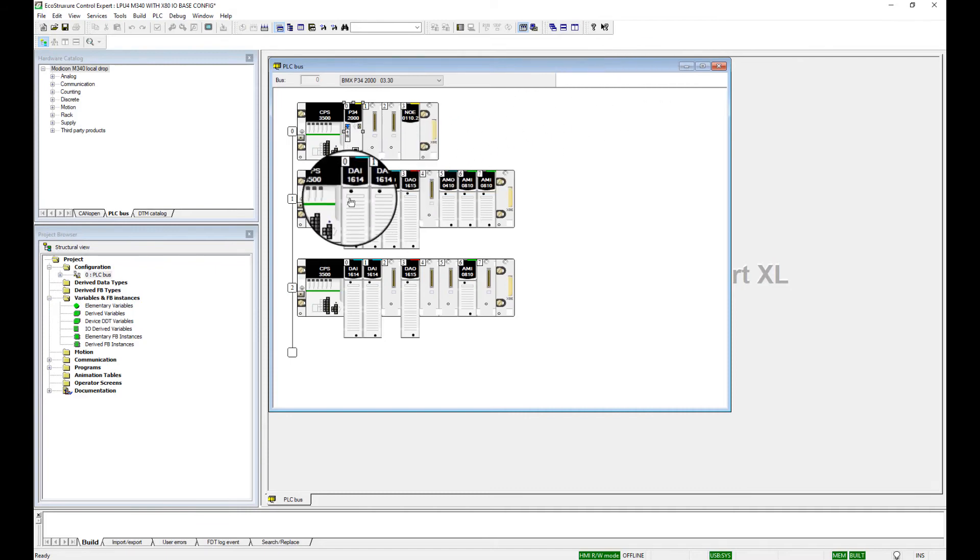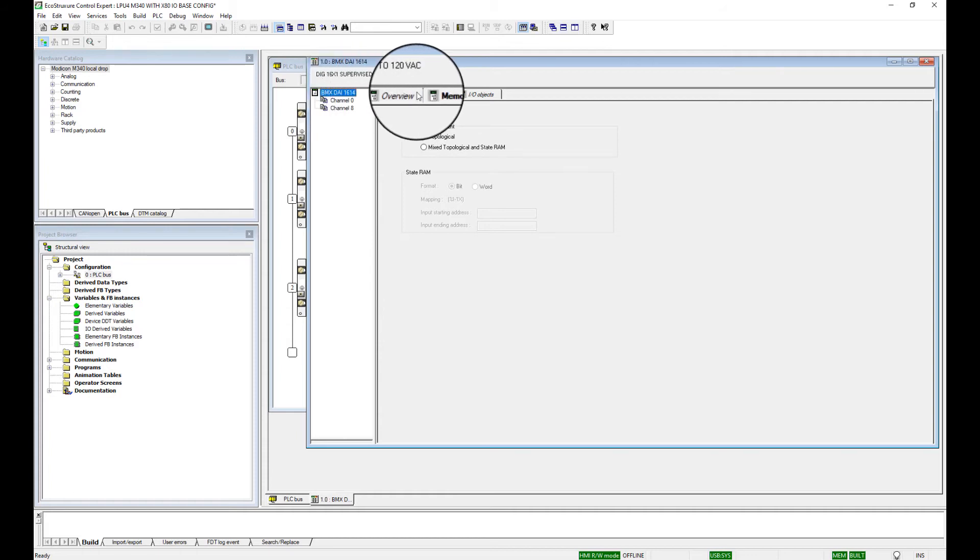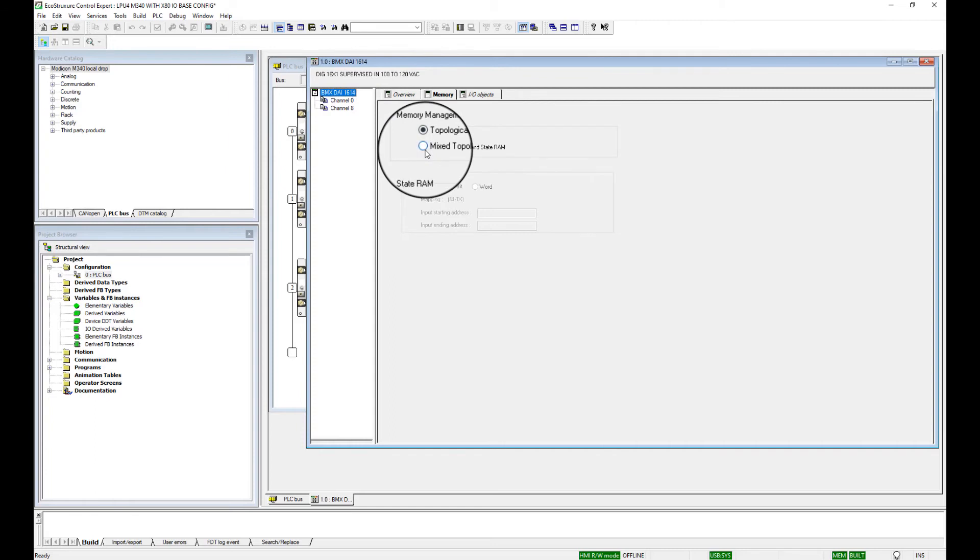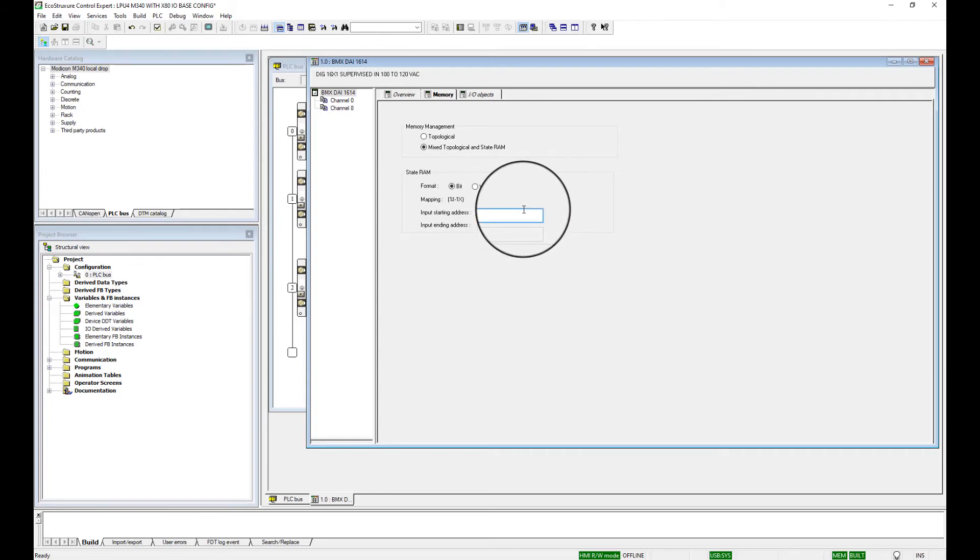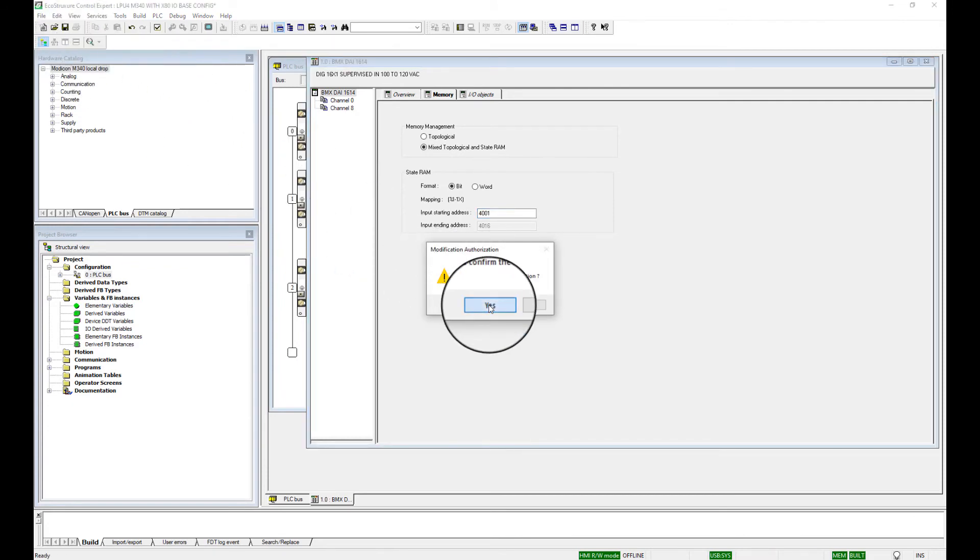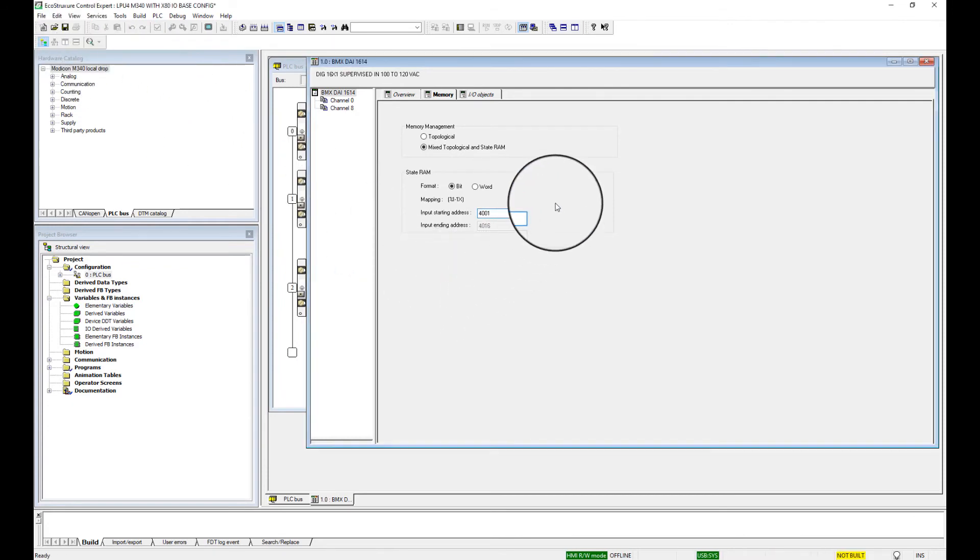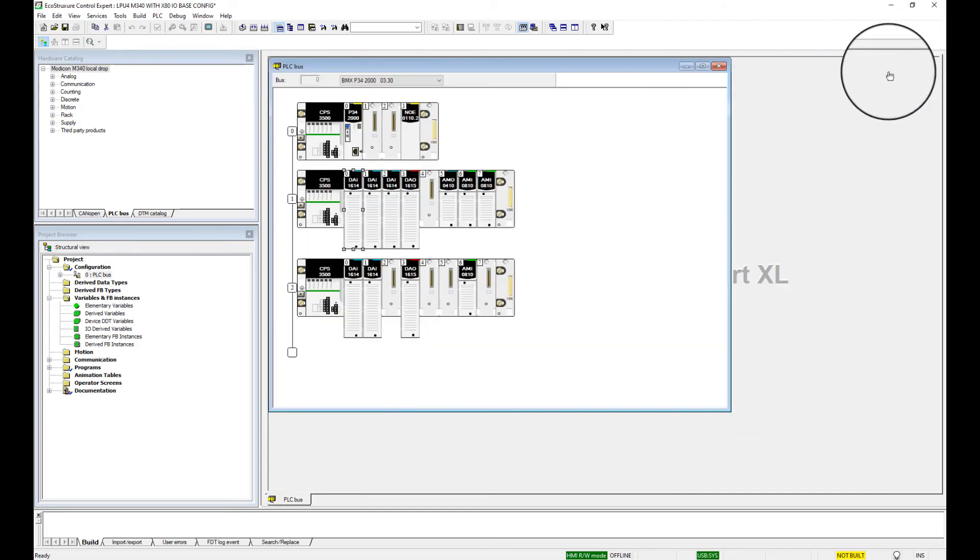Next, we want to set the configuration for the I/O modules. Double-click each I/O module and select the module description in the top left-hand corner. Go to the Memory tab, and in the Memory tab, select Mix, Topological, and State RAM. Set the State RAM addresses equivalent to the Quantum I/O that the X80 cards are replacing. The first Quantum I/O card state RAM address was 4001-4016. So I'll just enter that in here, and then we will validate this card. So now we have the 4001-4016. Close the I/O configuration screen.